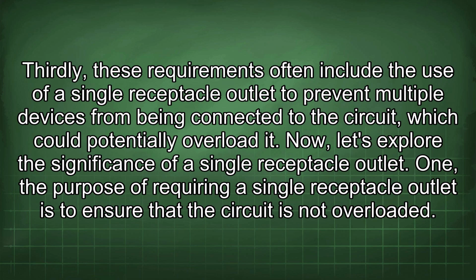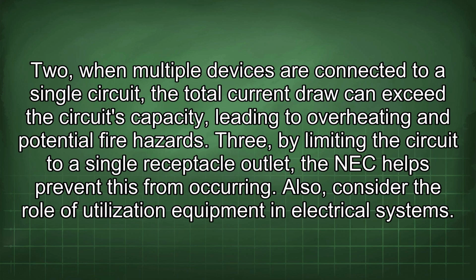Now, let's explore the significance of a single receptacle outlet. The purpose of requiring a single receptacle outlet is to ensure that the circuit is not overloaded. When multiple devices are connected to a single circuit, the total current draw can exceed the circuit's capacity, leading to overheating and potential fire hazards. By limiting the circuit to a single receptacle outlet, the NEC helps prevent this from occurring.